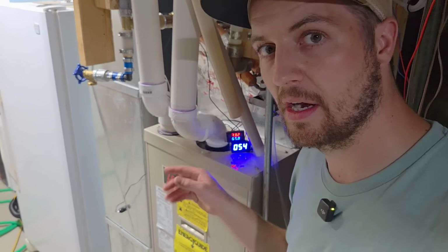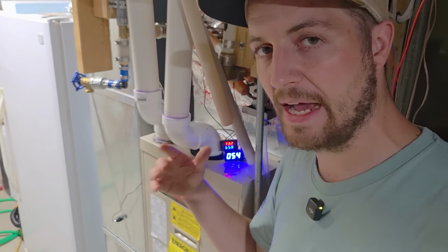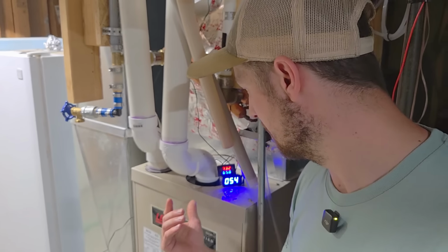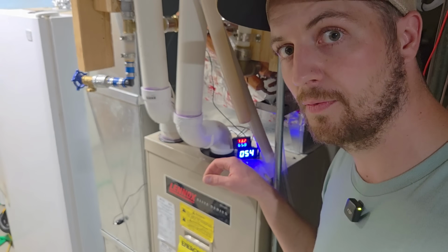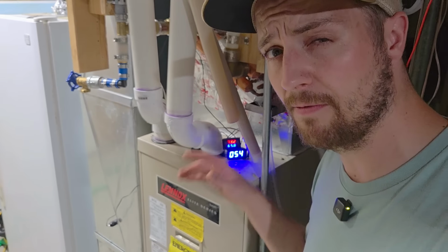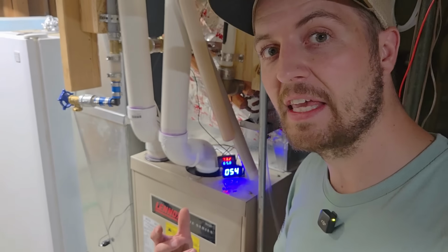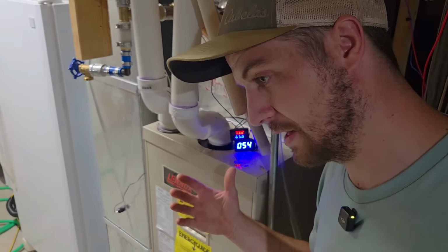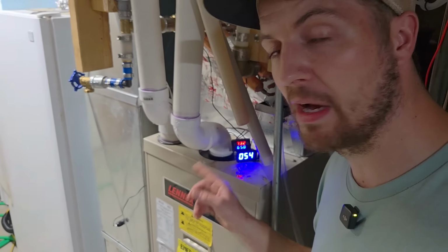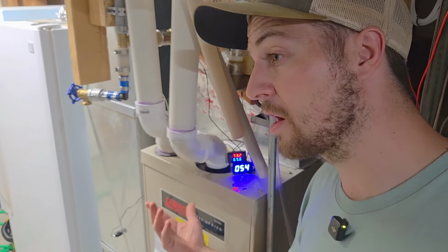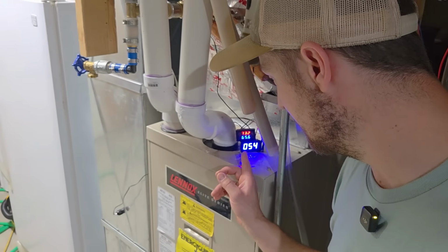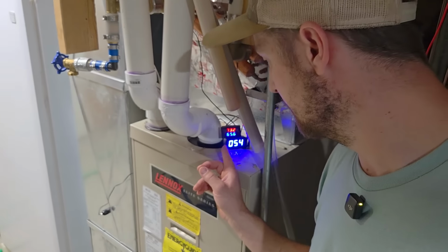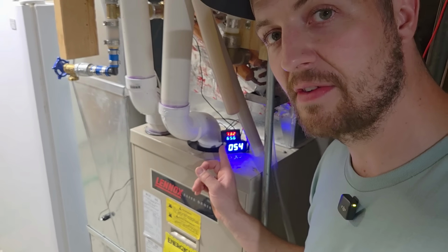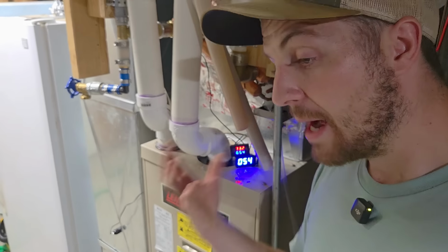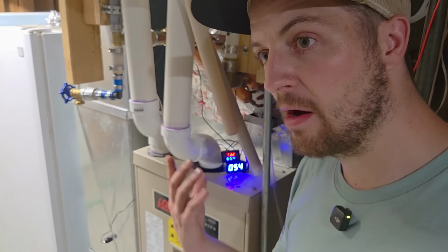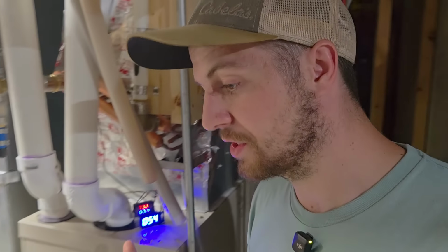Now, one last note on this. I'm running the window air conditioner units upstairs. That's why my incoming air is only 72 degrees. But let's say a geothermal ground loop field was big enough to maintain that roughly 55 degree water temperature coming into the heat exchanger, and let's say you didn't have any window air conditioners. Your incoming air temperature might be 80 degrees. If you had 80 degree air coming into the furnace and your heat exchanger is 54 degrees, what would your temperature split look like? It still might look pretty close to that 65 degree mark, which would not be the same as central air, but it might be about half the capacity of central air. I don't know, just things to think about.